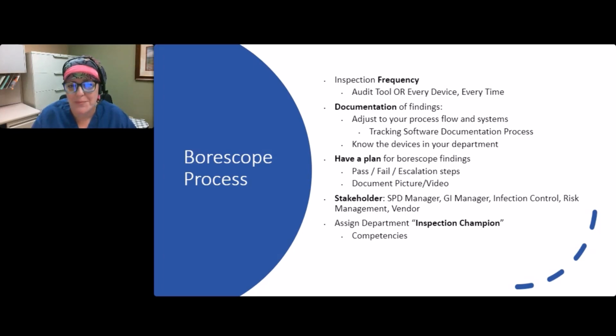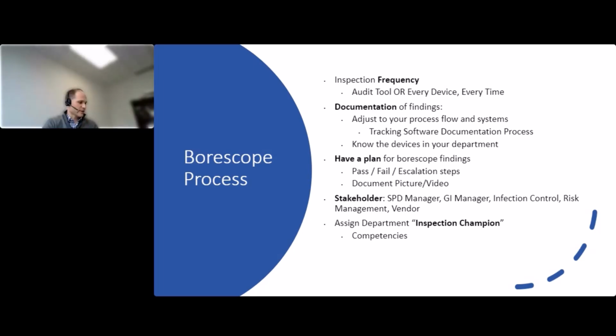Yeah, so great summaries there. Let me highlight a couple of those. So if we're looking with an audit hat on, auditing either the condition of these devices or how certain reprocessing steps are working, you mentioned potentially a new baseline of a brand new device coming into the department, where a borescope inspection might be helpful to establish what that device looks like brand new. You mentioned loaners in and out, inspecting those as they come into your possession. Repaired devices going out for repair, coming back in, establishing what that baseline out and baseline in might be is something that you mentioned.